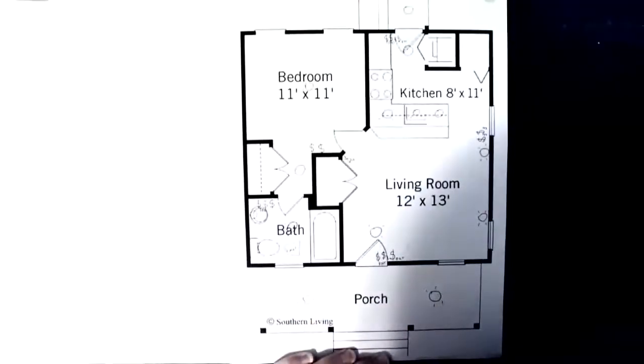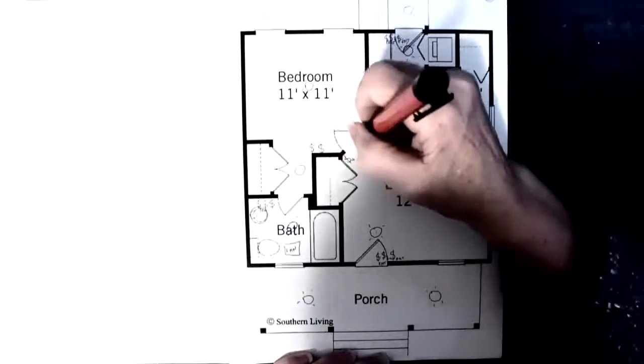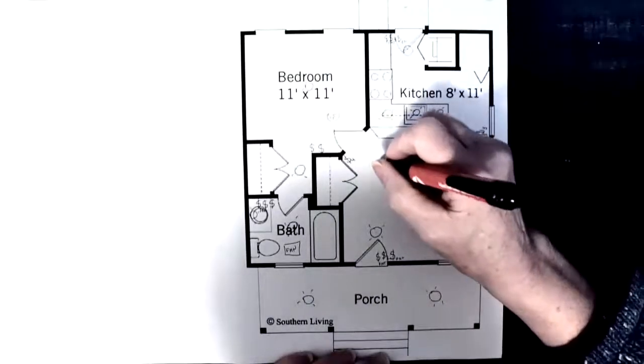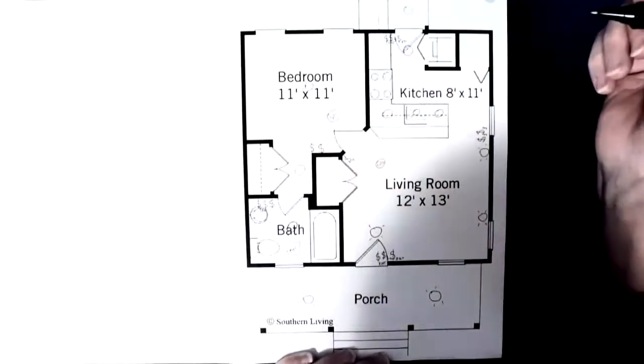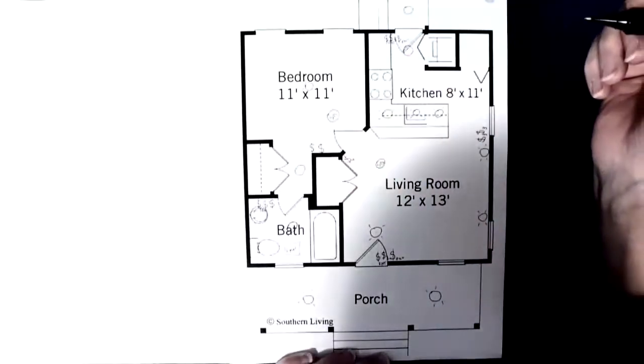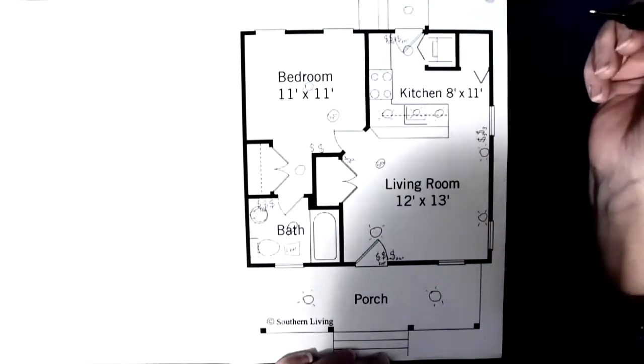Now the other thing I'm going to need is the smoke detectors. And the smoke detectors are in the national building code. So we need a smoke detector when we first enter a bedroom. And we also need a smoke detector before we enter into that bedroom. If there was gas appliances, also need carbon monoxide detection as well.